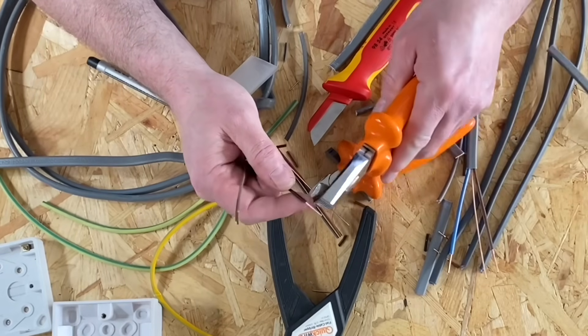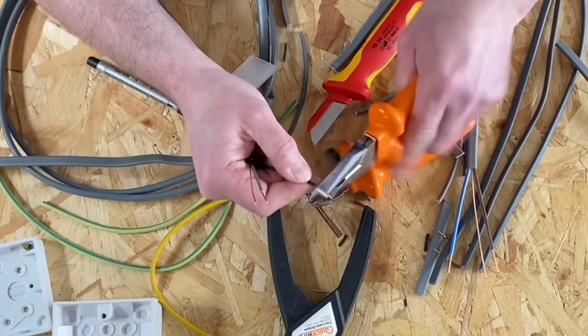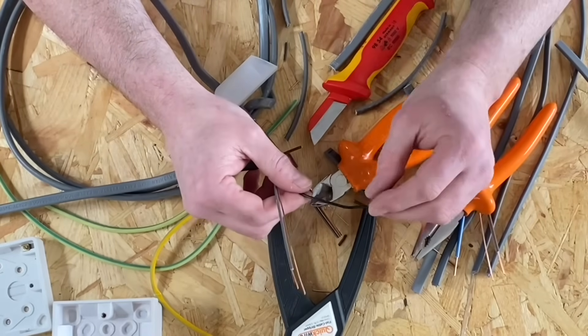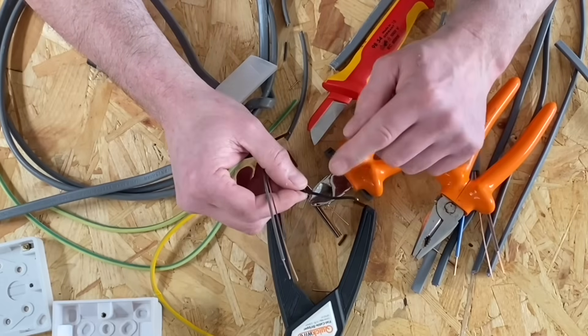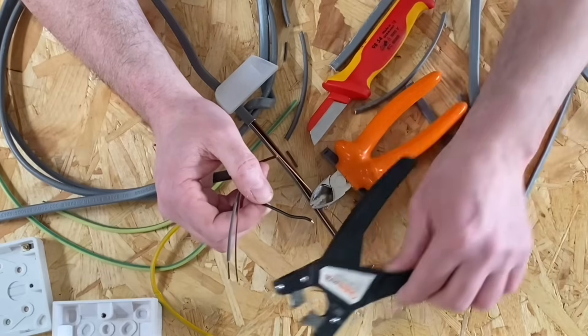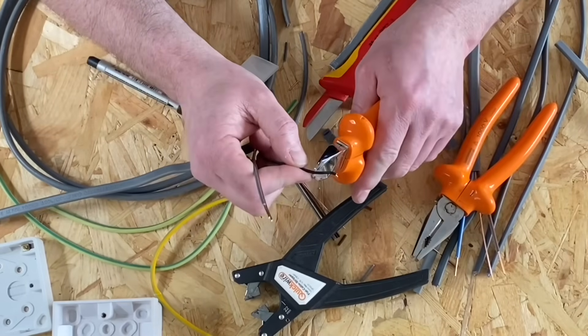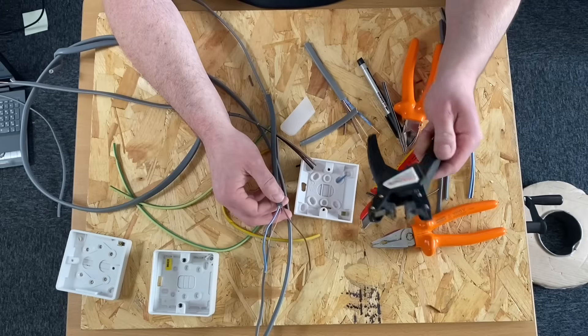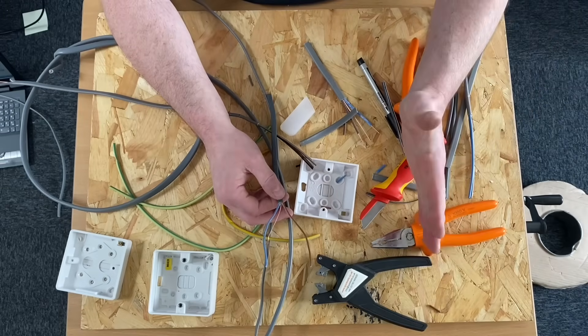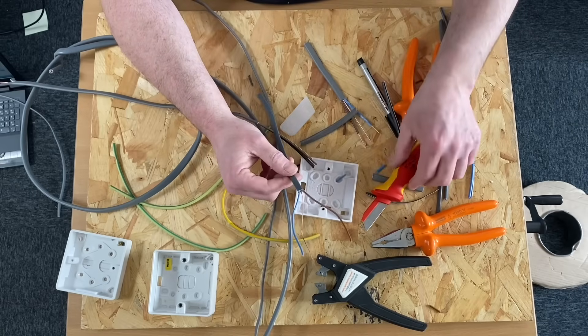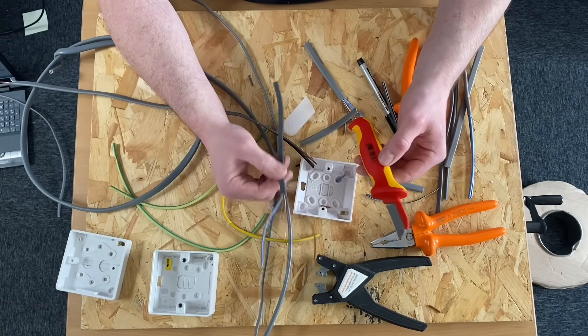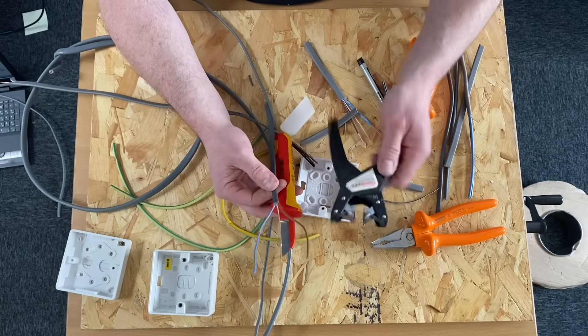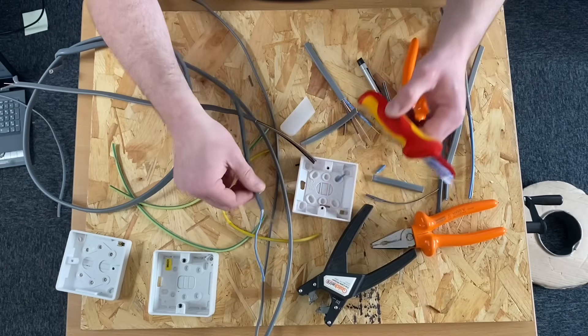Let's see if this one's work hardened. So, I don't think it has, but again, I can eventually get it to break. Nope. Ah, and it's broken. So again, is there a conversation to have about how hard you press with the knife? Yes there is. Is there a conversation about using these wire strippers? They're very good, but very limited. Can we get our students to use side cutters or pliers? Not early on, because they tend to do that when they're learning to strip them back. This only goes up to 2.5 is what we said. So again, once we get to 4 and 6 mil, they've got to come up with a technique in order to strip the cables and that would be the technique that we've just looked at. So learning to use the electrician's knife early on and then maybe owning a set of these in the future is a good way to build in the skills required before going to a tool that makes it a lot easier.